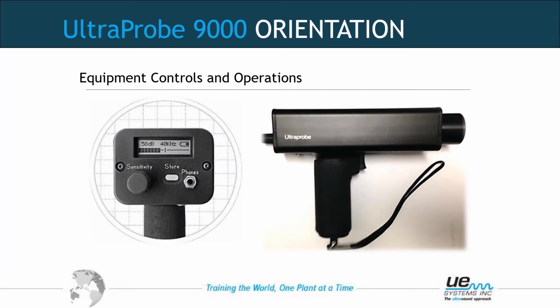The Ultraprobe 9000 is a pistol grip ultrasonic inspection unit. It has a pistol grip for ergonomic use, a trigger for on-off, as well as a sensitivity adjustment knob that is spin and click to select and to adjust, as well as a storage button. It also has a wrist strap that must be worn during inspection. Never leave the wrist strap dangling, as it poses a hazard in rotating or electrical equipment.